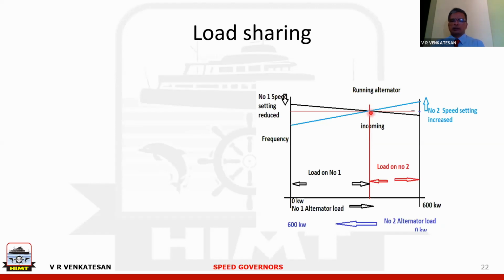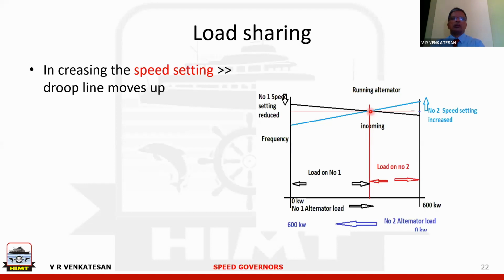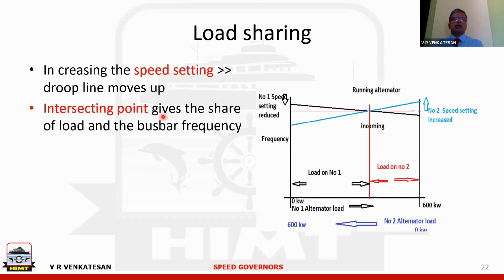What does this intersecting point represent? It represents the running position. So this one line has gone up, the other line has come down. This is the intersecting point. The intersecting point gives the share of the load, that is, how many kilowatt is shared to number 1 generator and how many kilowatt is on number 2 generator. And it also gives the busbar frequency. So in any parallel running alternator, the droop lines where they intersect gives the running condition. And what we are calling running condition is this many kilowatt on the incoming generator, which is number 2. For example, this can be something like 200 kilowatt, and 400 kilowatt is remaining on number 1 alternator. And the busbar frequency is here.